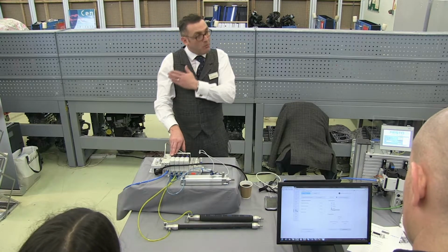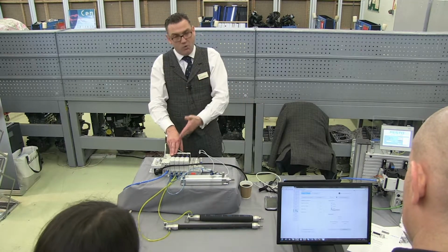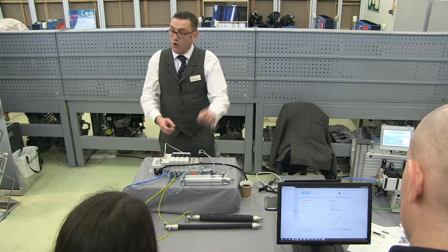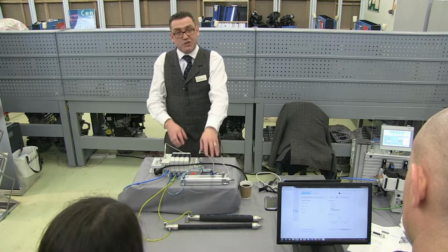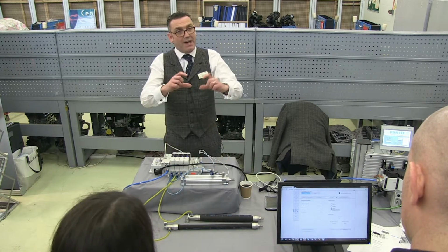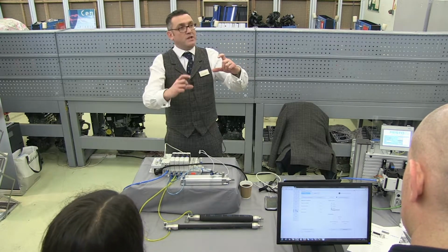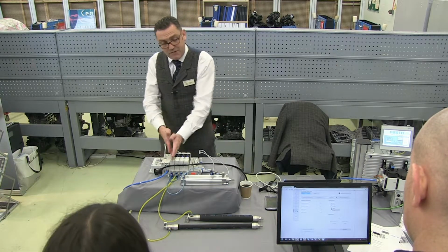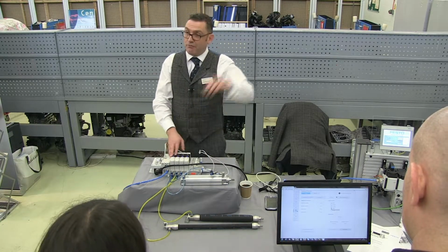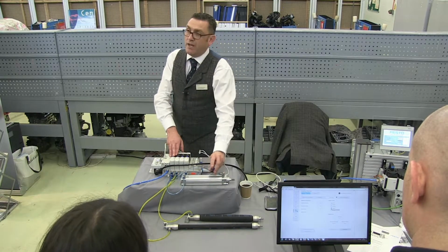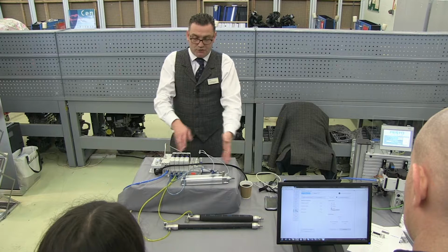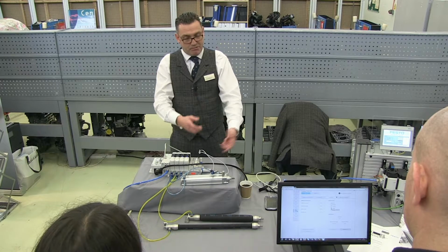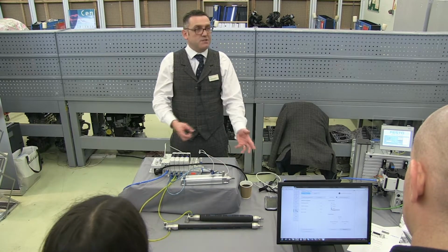What I can then do as part of my maintenance schedule, or maybe even at a shift changeover, or if you change a job, format change, whatever it may be, you can put it into your machine control to automatically run a diagnostic test. What it'll do then is compare the original one to the diagnostic one, and we can flag that up as an alarm then to the system. So we've identified in this case that there's a leak, and we've flagged that back to our main control, but equally we've compensated for that leak, which means from a production point of view, we're maintaining productivity. We're not losing production efficiency because we've got leaks in the system.